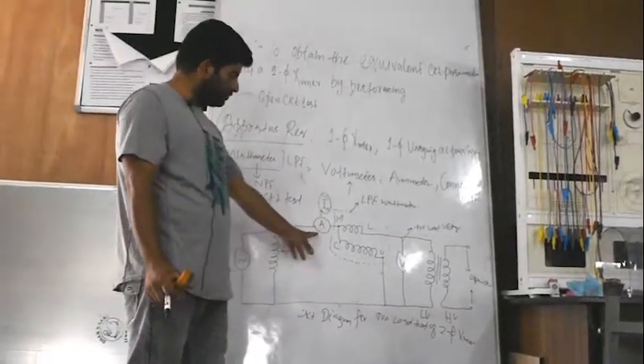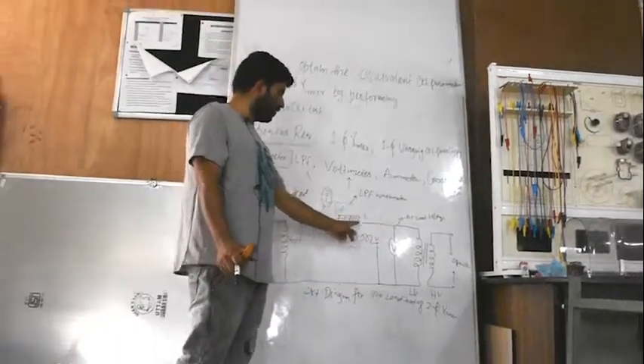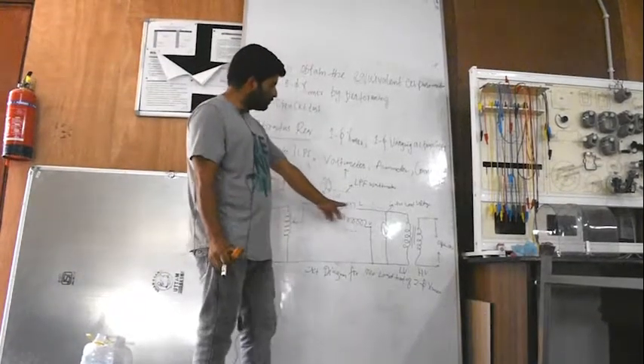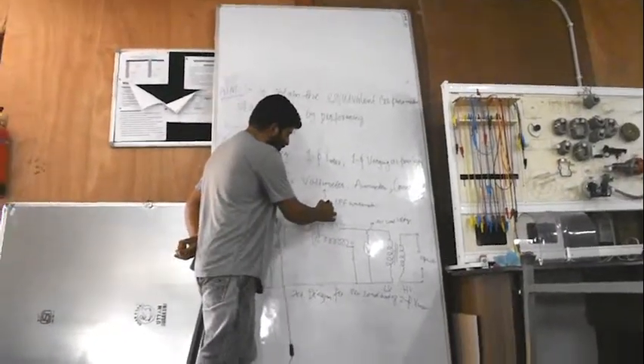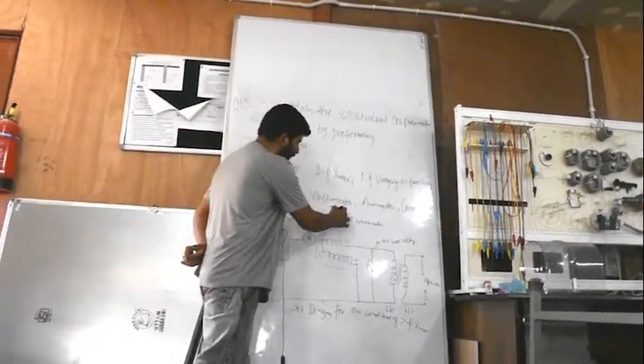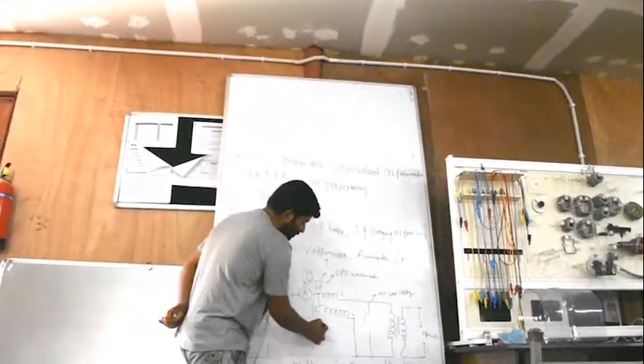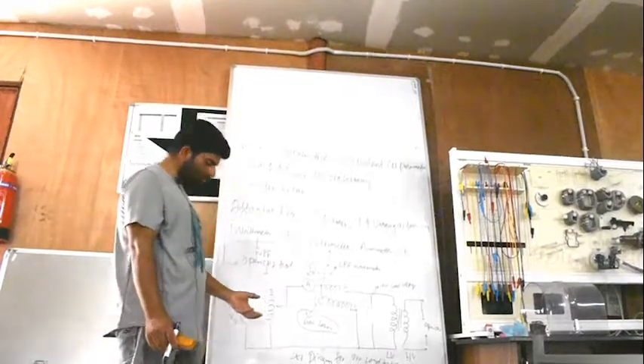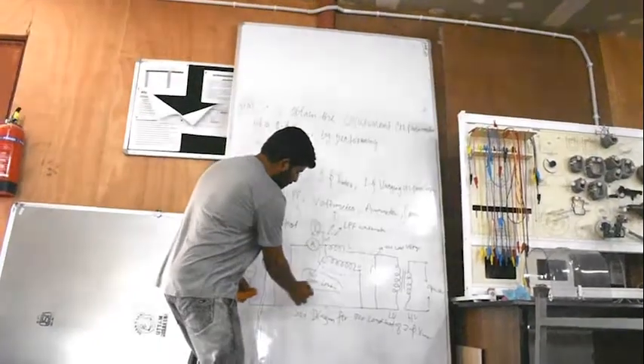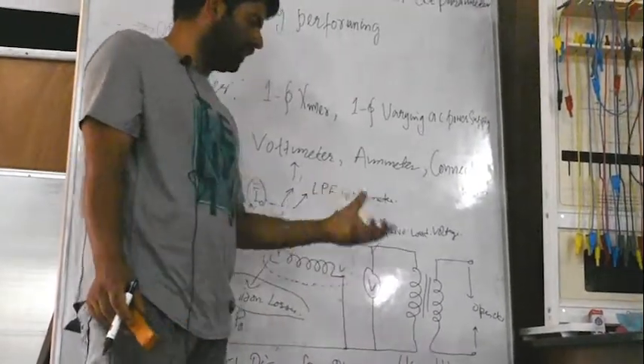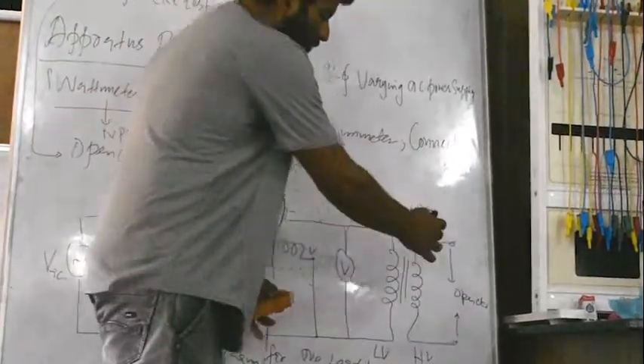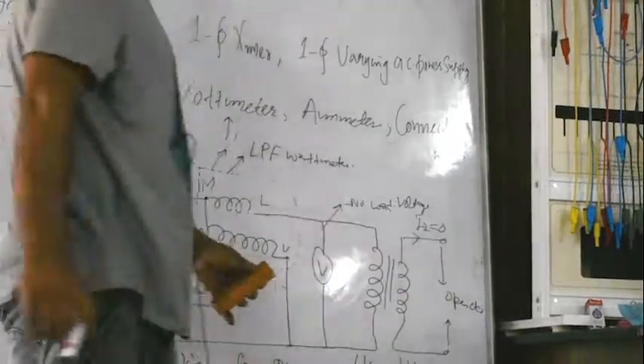After that we will be connecting an ammeter which will keep track of the no load current. We will be connecting the wattmeter, which has 2 coils, the current coil and the pressure coil, which will measure the power consumed by this transformer at no load, which at rated voltage is nothing but the iron losses. The wattmeter reading actually reads iron losses. The basic purpose of the no load test is to obtain the iron losses occurring in the transformer, usually represented by P naught or W naught. This meter will read the exciting voltage, or the rated no load voltage, by which we will be exciting the transformer, and the secondary side will be open circuit, that is, I2 or I load will be 0.